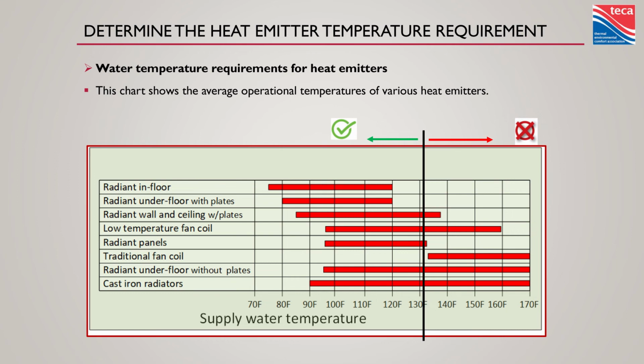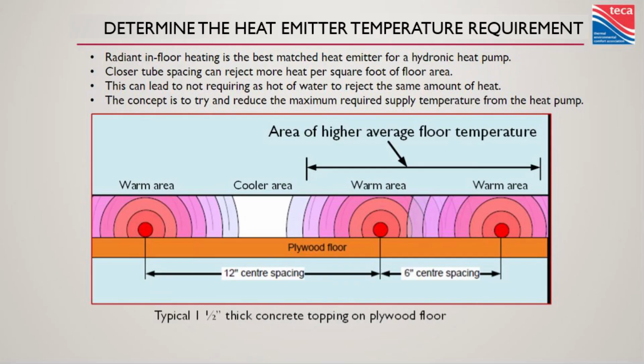So if we're talking radiant floor heating, more pipe. I don't sell pipe. There are some nice people here who do. This is not a pitch for pipe, but it's the cheapest thing in the whole system. Put more in and you can increase those surface temperatures with the same water temperature. Or, to say another way, lower that water temperature to get the same output.